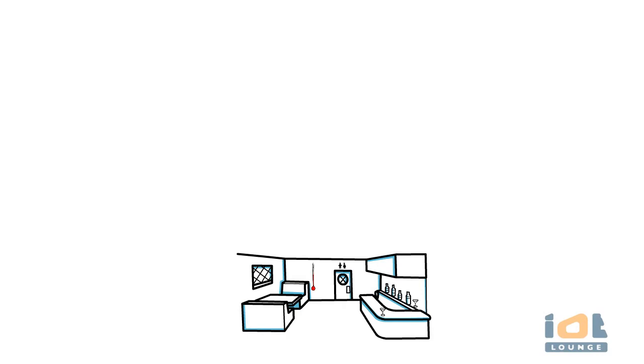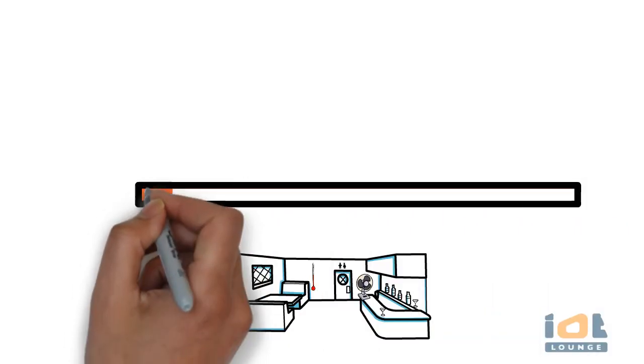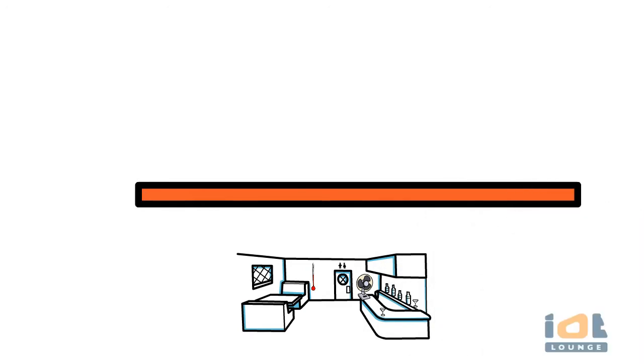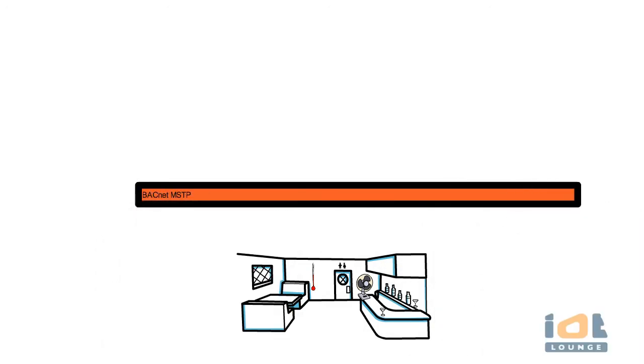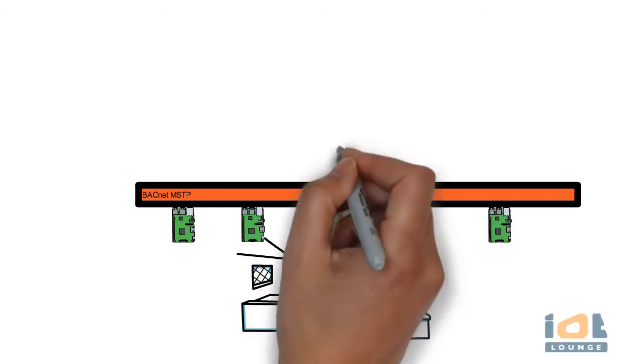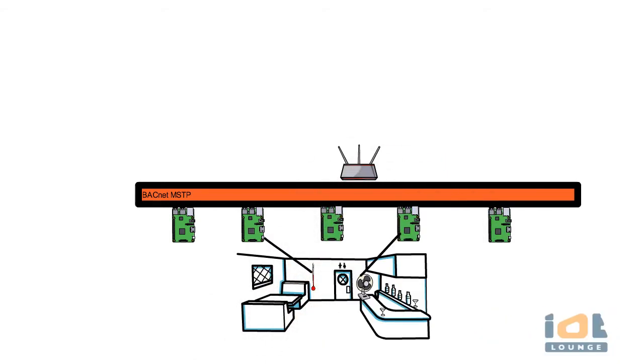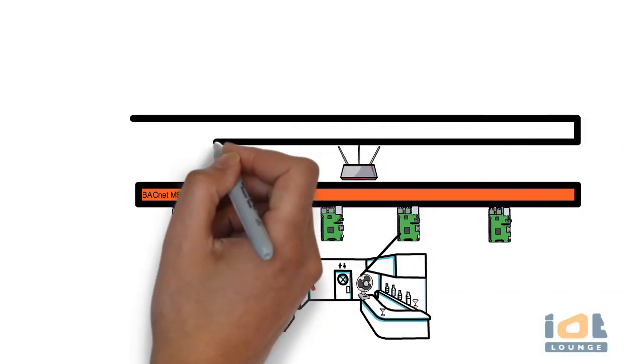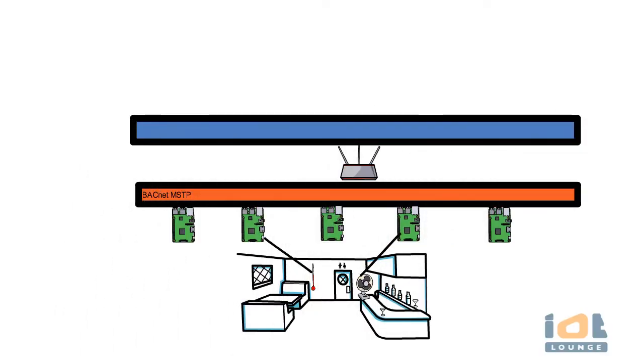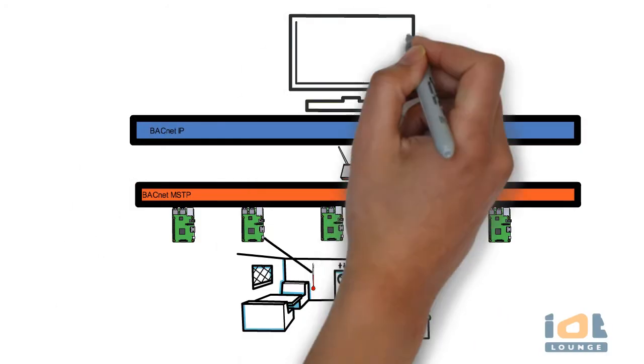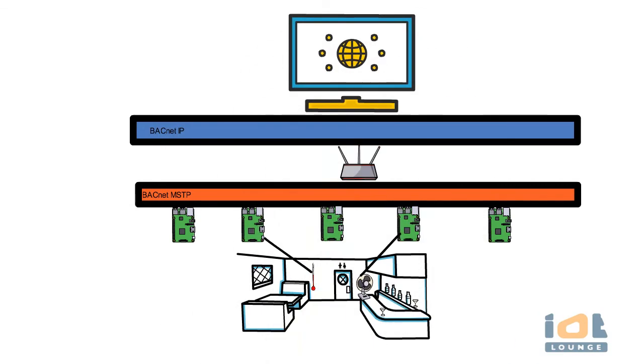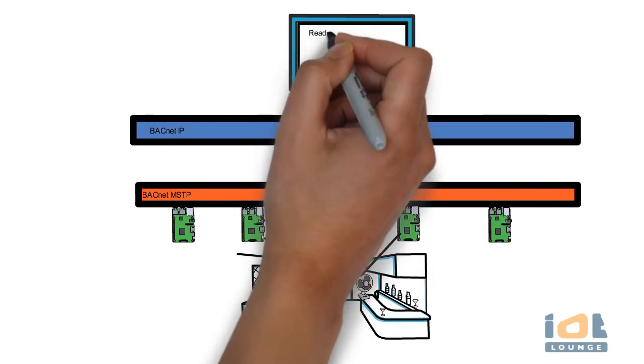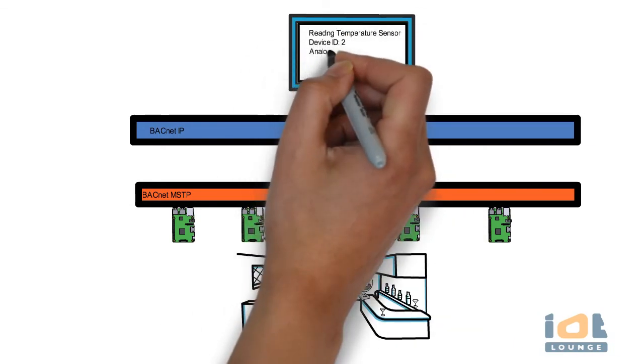Enough of the theory. Let's examine BACnet in action in real life example. The typical architecture of a BACnet system consists of HVAC equipment and sensors around a building connected to a series of field programmable controllers communicating in MSTP. The data is presented in a presentation layer in a BACnet enterprise software residing in the IP layer of the network. The data is traversed between MSTP and IP layer using BACnet router.